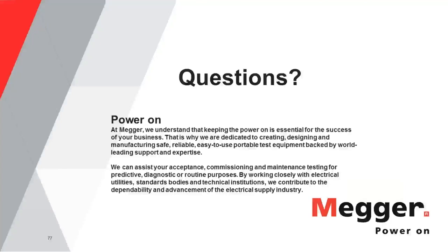And another thing in consideration is whether equipment has been operating or not. So if you came in the morning and the facility has been de-energized all night and you tested a motor, for instance, you'll get a pretty high reading most likely. If the motor had been running half of the shift and then you shut it down and immediately do a test, obviously it's going to be warm, and so the reading is going to be decidedly lower. So yes, take temperature into consideration. You can correct to a common temperature base and store records that way, and definitely include in test results the temperature at which the test was taken.